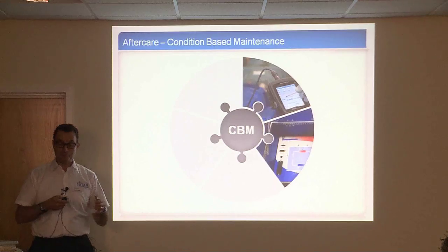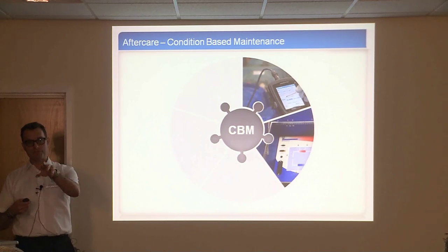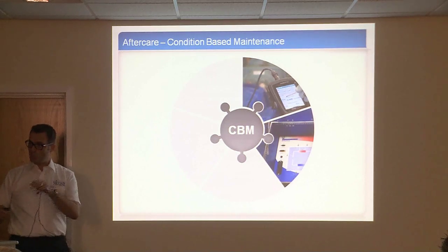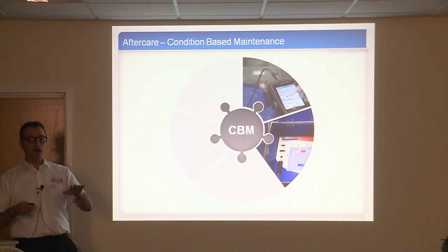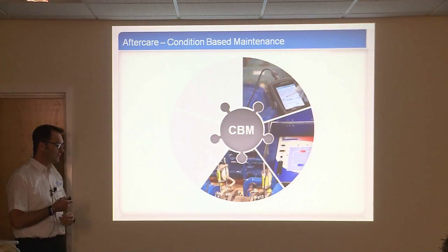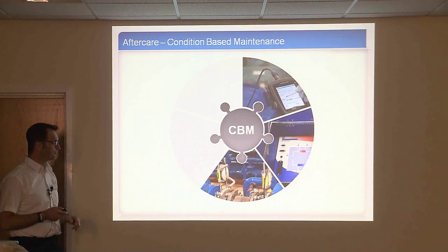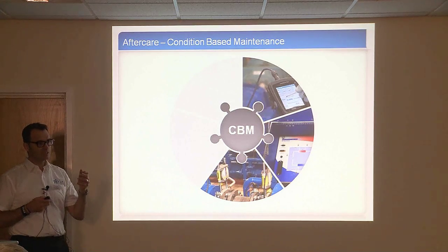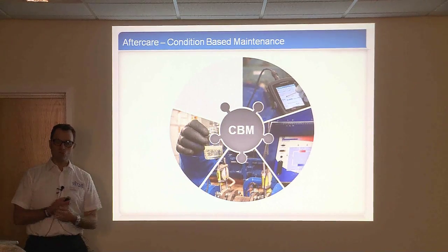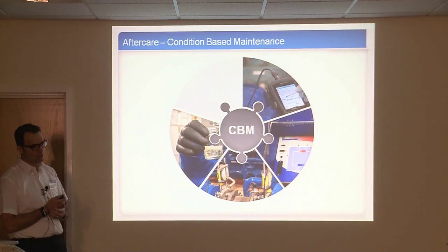But also that can be pulling that information off-site for us to monitor weekly. And we've got some graphs, again, at the back of our data monitoring system. And we can see where the performance falls off on a plant and where we have to go and do some invasive work on compressors and so forth. Laser alignment, again, we've got at the back, so we can have a look at that. And then the last two elements are oil sampling and also refrigerant quality checks. This one is what we call an ARQ, which is an ammonia refrigerant quality check.